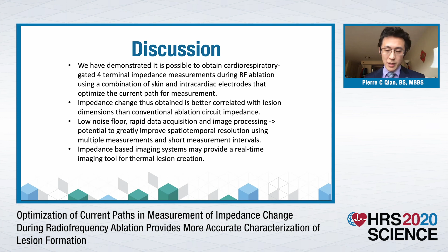The low noise floor and rapid data acquisition and processing times mean that there is scope to greatly improve the spatial temporal resolution of the system by taking multiple measurements using various combinations of intracardiac and surface electrodes. We're using shorter measurement intervals to give greater temporal fidelity. As such, an impedance imaging system may provide a real-time visualization of ablation lesions created in the EP lab.